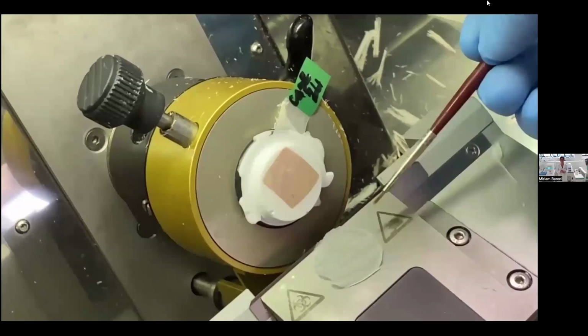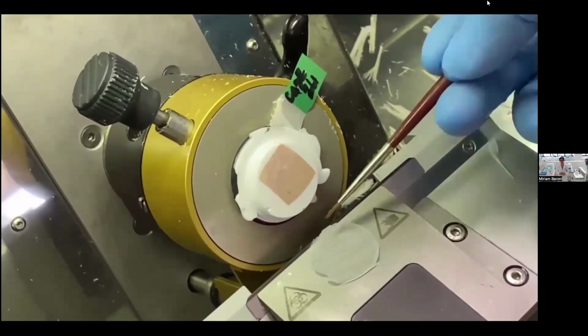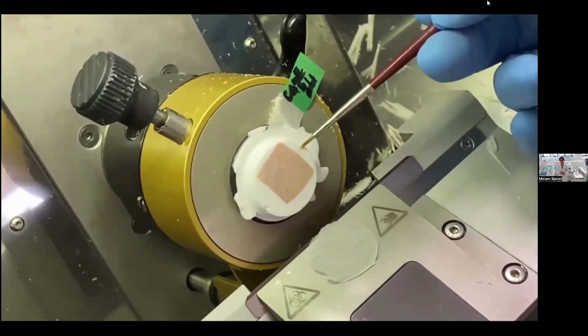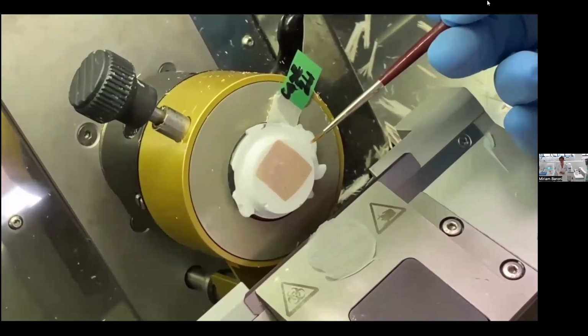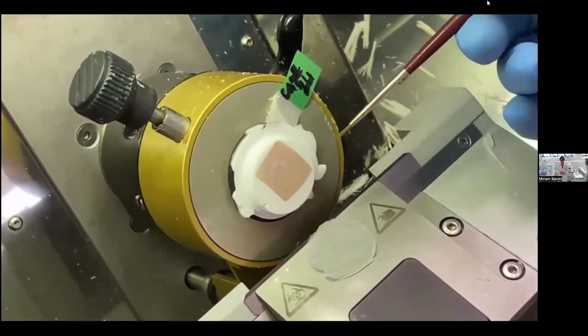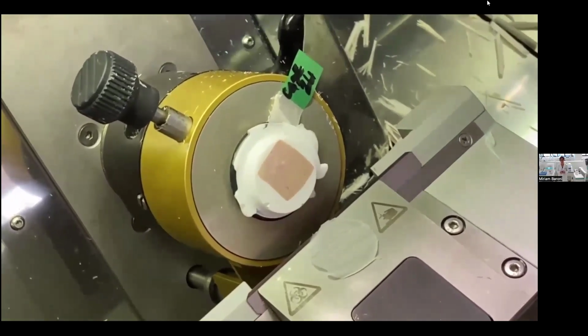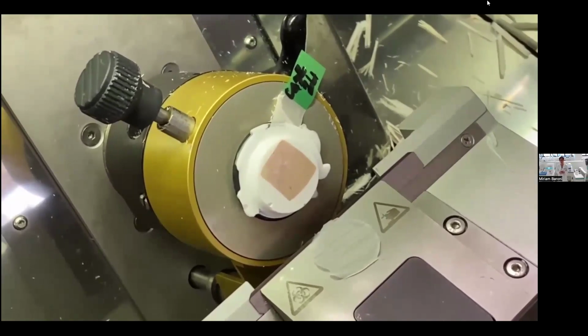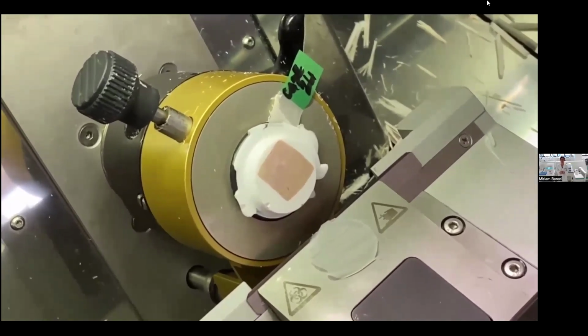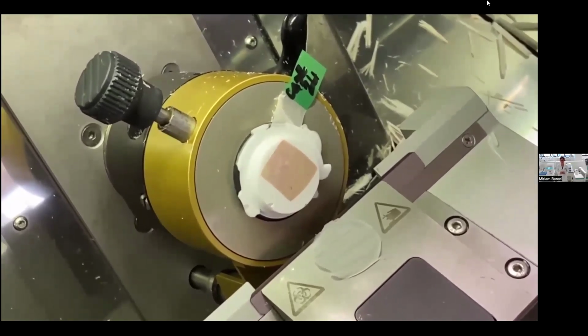In fact, if I needed to freeze a more delicate sample such as brain, which is better sectioned at minus 15, 16 degrees, I can reduce the freezing time in the PrestoChill to stop the cooling curve earlier and have a less cold block, but anyway of good quality.